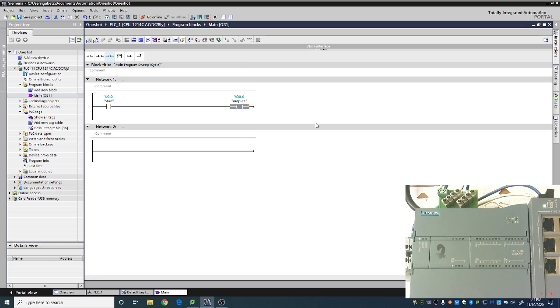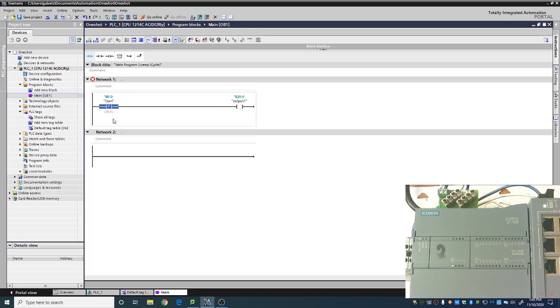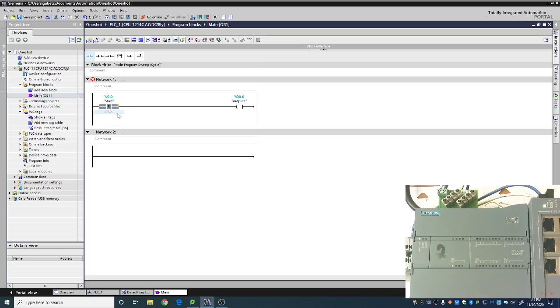To put a one-shot in, how I like to do it at least, is I like to just change my make to it. So I have a start button here with a make, and I'm just going to double click, and we're going to go down to P, and this is a positive transition. So we're going from, we're looking for that transition from a zero to a one. And you will notice now that on the screen we now have some red question marks that we need to put in.